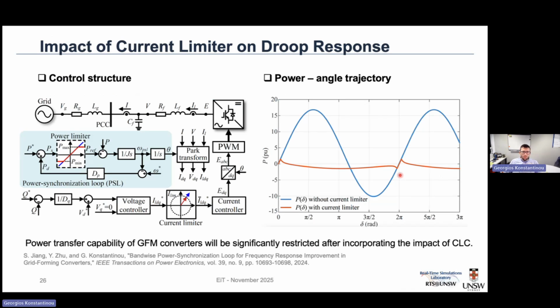The reality is that when this happens, we do have a direct impact on the synchronization structure and the synchronization behavior of a grid forming converter. That is because what was an ideal P delta curve, which you should be familiar with from synchronous generator behavior, changes substantially. So the current limited grid forming converter behaves as this red line, and this red line also depends on the voltage that it sees at its terminals because of the faults that exist in the network. And this, as you can imagine, complicates the analysis that we have and the level of complexity that we need to address in this system.